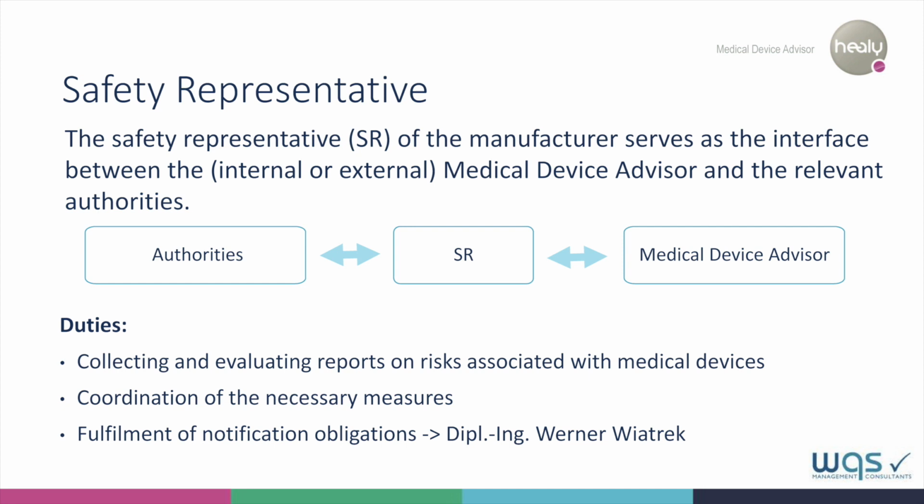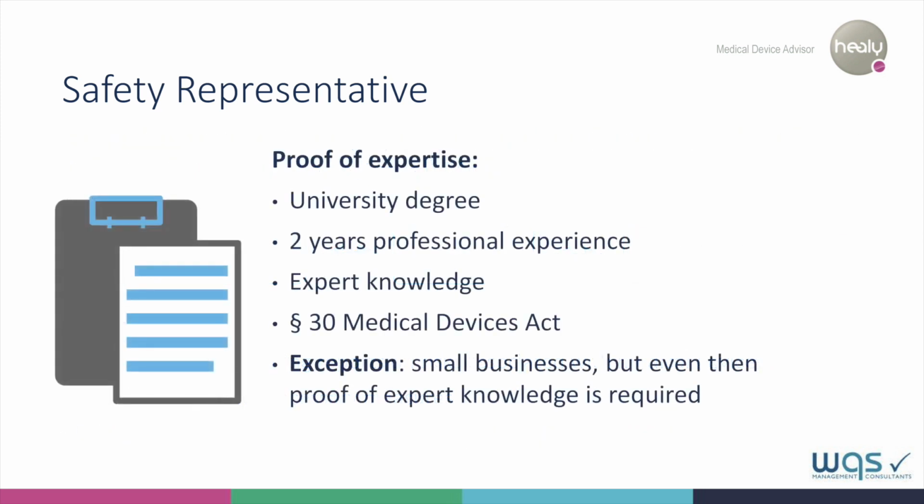As a mediator between the authorities and the MDA, the SR has the following tasks. He or she collects and evaluates reports regarding the risks of medical devices, coordinates any necessary measures, and fulfills the notification duties. The SR at Healy World is engineer Werner Vietrek. The prerequisites to become an SR are graduation from university and at least 2 years of professional experience acquiring the specialist knowledge required by paragraph 30 of the German Medical Devices Act.